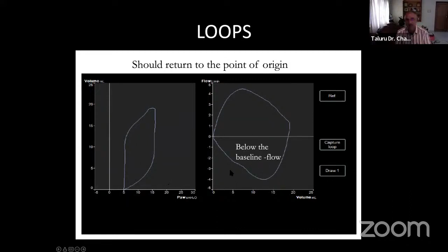See, this is the square wave. This is the one we had. This is a decelerating. This is pressure controlled because it is touching the baseline and cycling. Whereas in pressure support, it is cycling above. It's a flow cycled one. If you consider the peak flow as X, at 25% of X, it always cycles. Both are decelerating, but this decelerates and touches because it is time cycled. It has to touch the same baseline and then only cycling occurs.